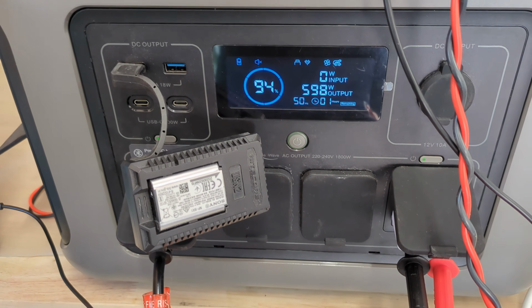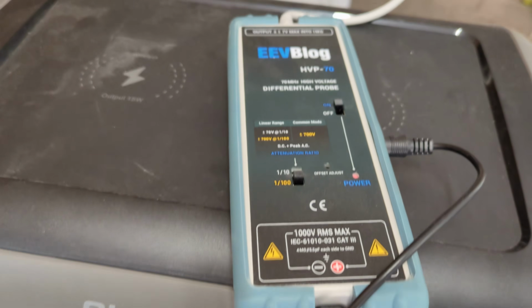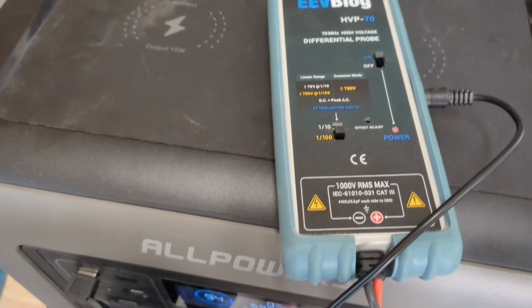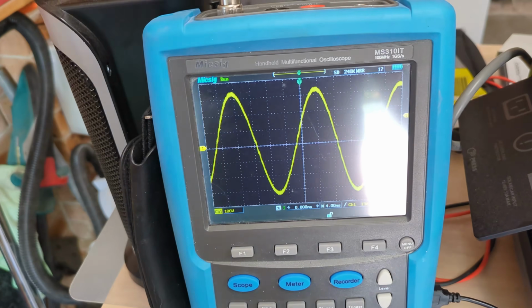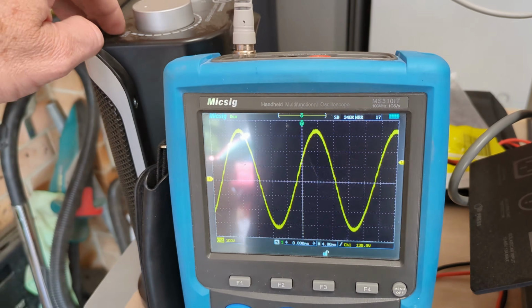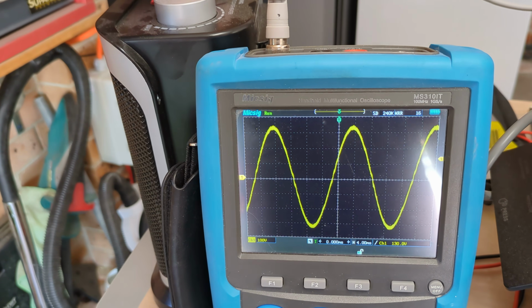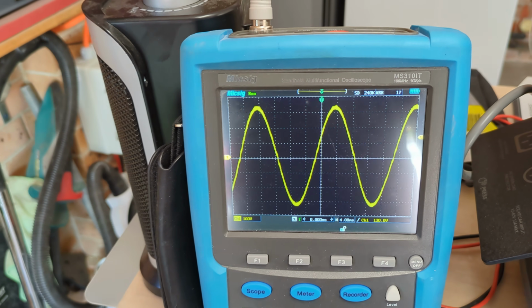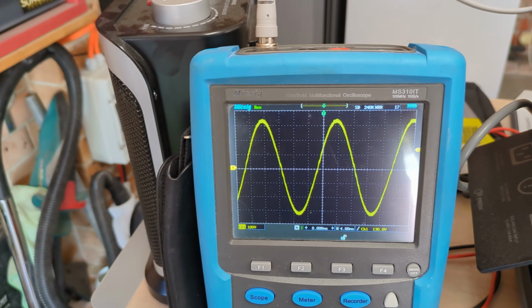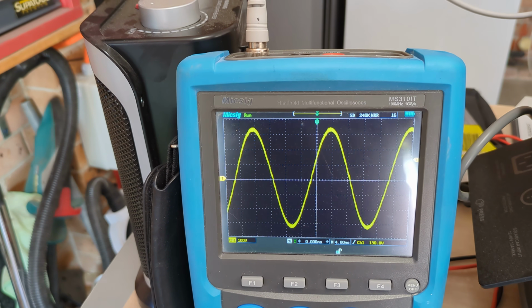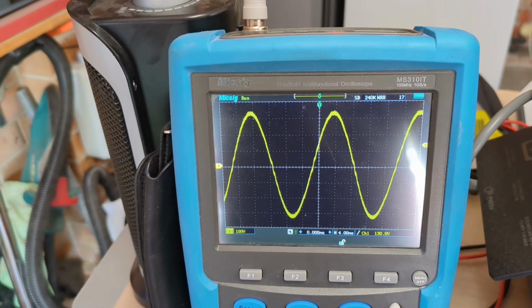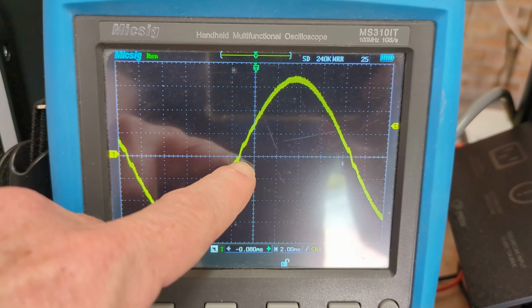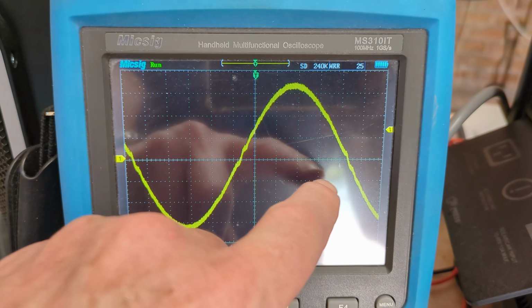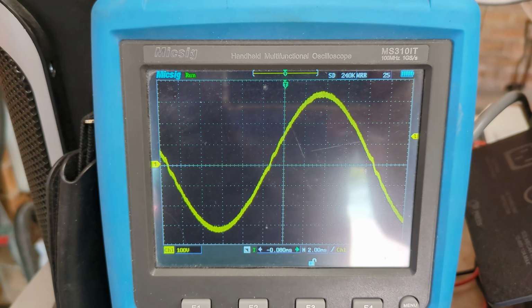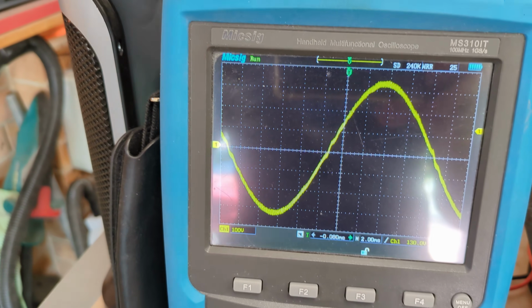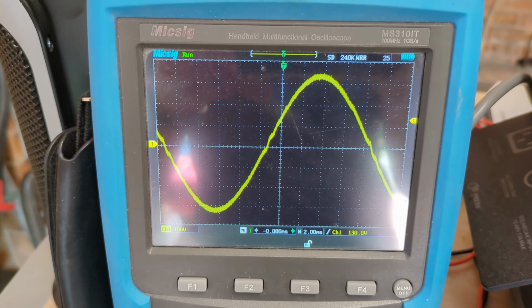All right, let's do a sine wave test. I've got my high voltage differential probe plugged into the mains output here, and my heater switched on, and you can see it's not too shabby at all. That's half power; this is the full, 1.2 kilowatts or so. Sine wave, no problems. There's a little bit of crossover noise here, but it's neither here nor there really.